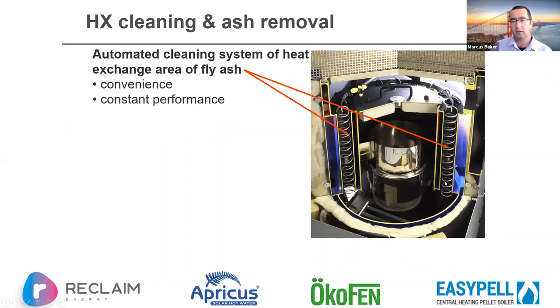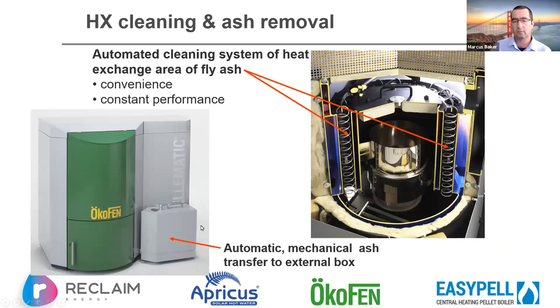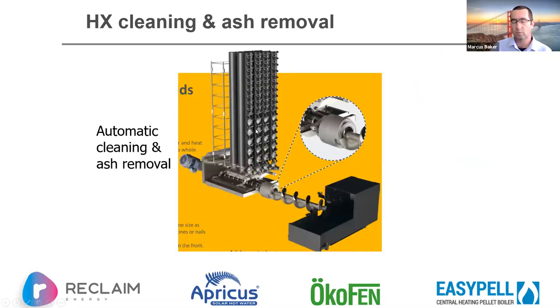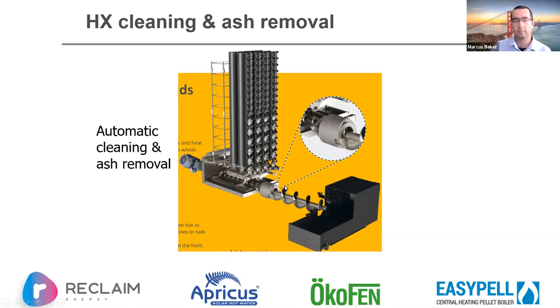Heat exchangers are cleaned by a reciprocating spring system that moves up and down with a clang, dropping fly ash that has built up. Ash is then mechanically transferred to an external box. The Etta boiler is very similar in this regard. In the Ökofen context, turbulators go all the way up, providing turbulence and cleaning so any fly ash that settles is knocked back down, then augered out to an external box.